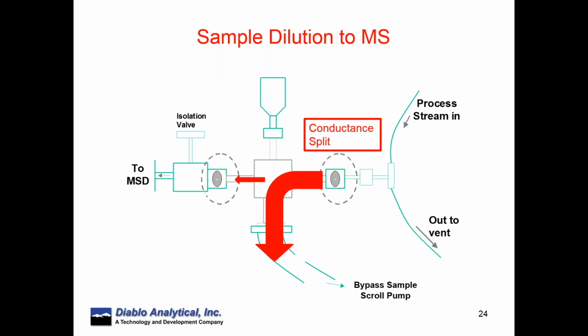So this is an example. The red arrows remind us where the sample's going. Most of the sample is coming in and going out the bypass pump, and a small but reproducible amount of sample is going into the mass spec through the second orifice. We sometimes call this a conductance split. It's a similar concept to splits we might run into in lots of instrumentation, but in this case, in mass spectrometry, we are dealing with conductance.